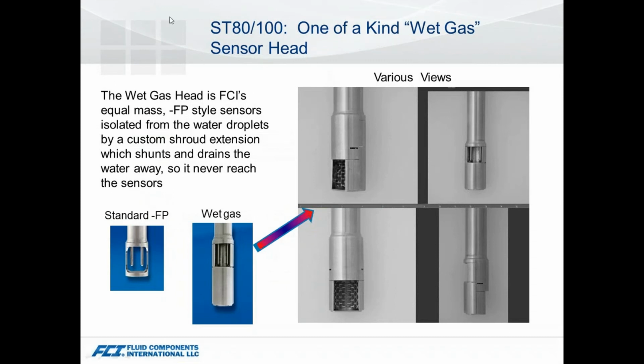So details of that wet gas sensor. You look at it, a standard FP sensor, we've got the thinner thermal wells. Really what we're looking at is just doing a mechanical knockout of the moisture in the line. We're taking an approach that leaves the sensor at its normal temperatures, as far as heating the RTD. If you look in the upper left here, you see the inlet side of it. In the lower left, there's a screen in there to help knock out some of the entrained moisture.